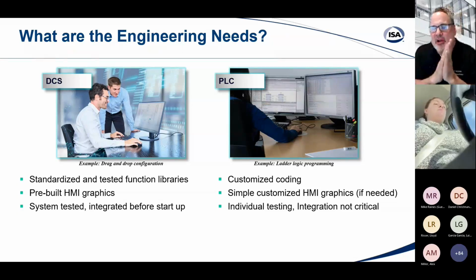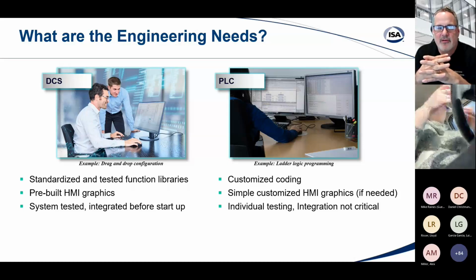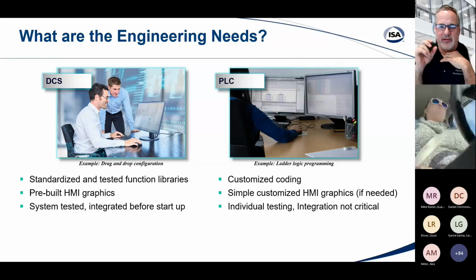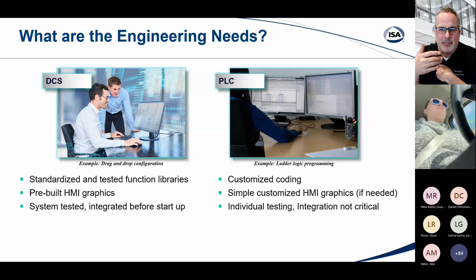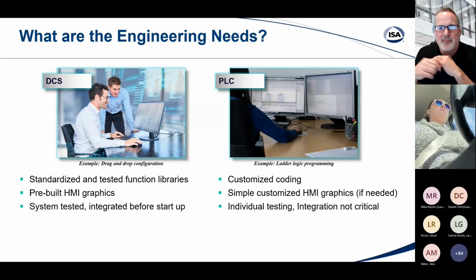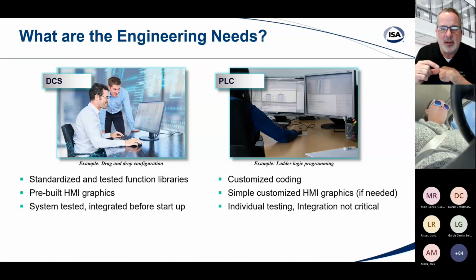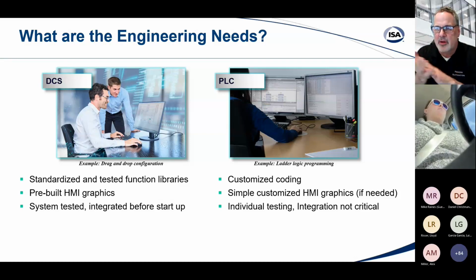And then you get down to the engineering side. What are your engineering needs? On the DCS side, you basically get a library of tested, certified, and standardized function blocks. These are the configurations that you drop down on the screen that do specific functions. For example, a time delay function, or a voting function, or whatever it might be. These have all been pre-developed, pre-canned, and you're just dropping them down on a screen. On the PLC side, typically it would require some customized coding. I was talking to one of the PLC manufacturers.